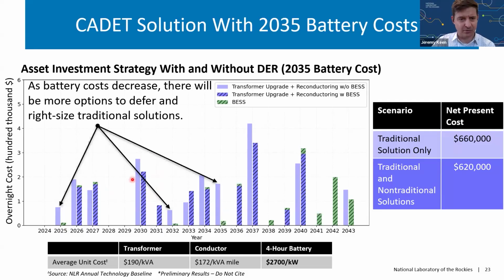We also see some years where there's just a reduction in the amount of investment in transformers and conductors when you have batteries relative to when you don't. I see this as an example of right-sizing. When I say right-sizing, I mean installing a new conductor, transformer, or other asset that's not too big and costly, but just big enough to meet the load demand over its lifetime. So the possibility of using batteries later means we can size the conductors and transformers smaller earlier on.